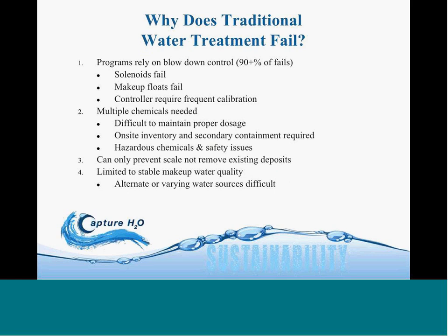The main reason is because they rely on blowdown control, water to be dumped back to the sewer, and that's where you have a lot of mechanical failures. Solenoids fail, makeup floats fail, your controllers require calibration. You need multiple chemicals. You have to maintain secondary containment, and you have to manage those chemicals by pumping them in. Number 3, and this is kind of a big one, is traditional water treatment prevents scale from forming, but it doesn't remove existing deposits.